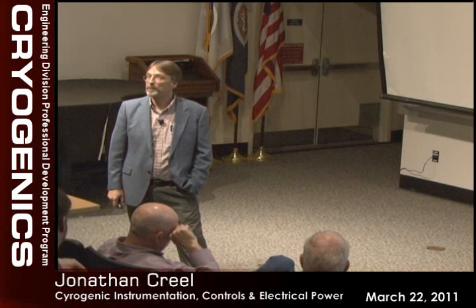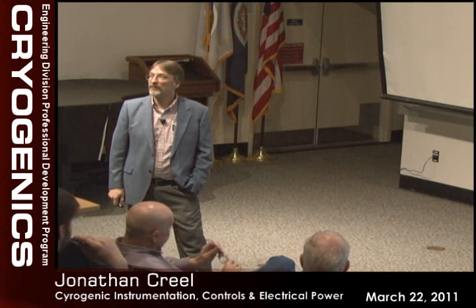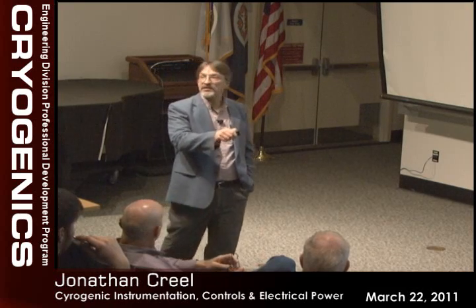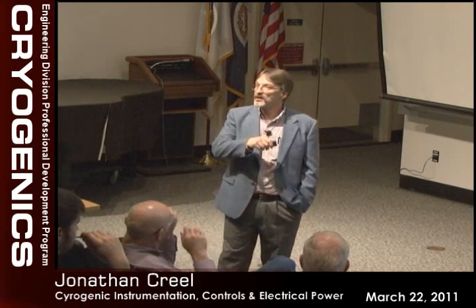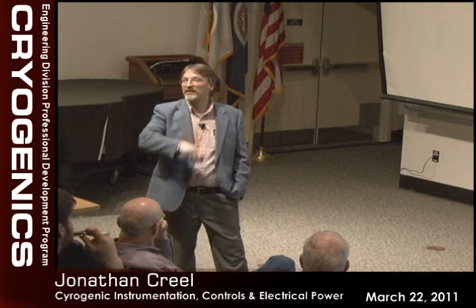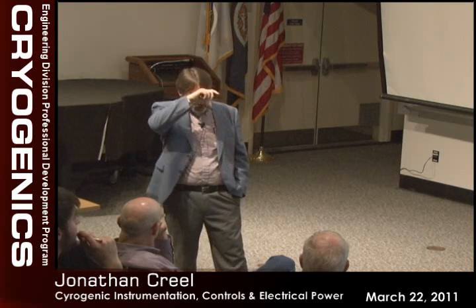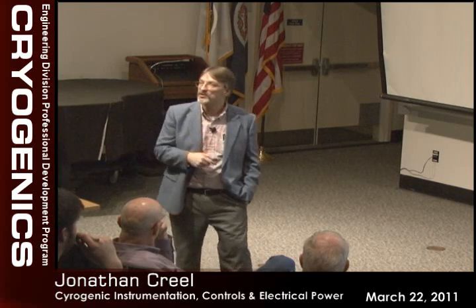The second part, did you put off any radio frequencies that shut down the walkie-talkies and everything else in the area? No, I haven't seen that with these. Yeah, well, VFDs will make horrendous noise. What happens with a VFD is it has a carrier frequency, just like a radio station.